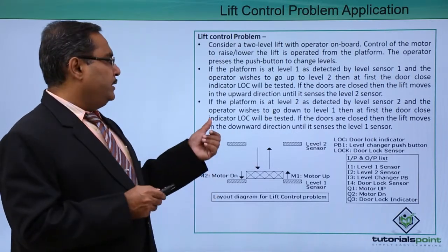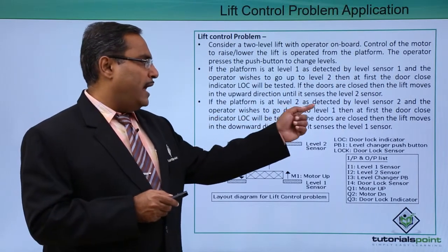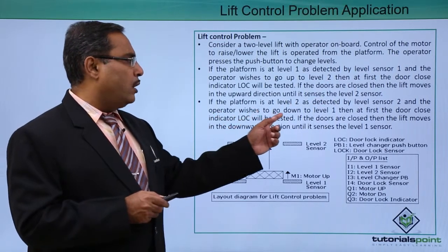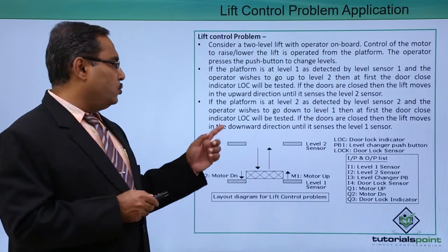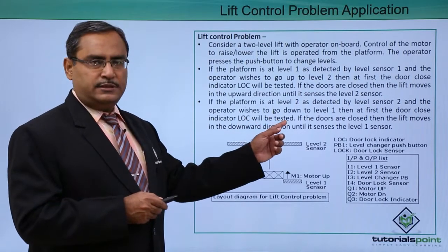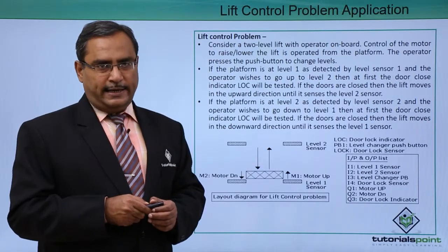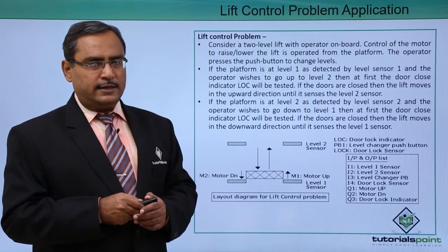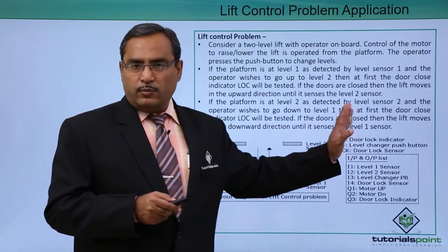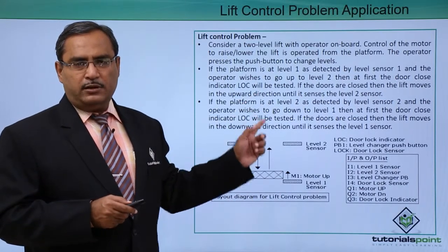In the reverse direction, when the platform is at level two as detected by level sensor two and the operator wishes to go down to level one, the door close indicator (LOC) will be tested first. If the doors are closed, the lift moves in the downward direction until it is sensed by the level one sensor.